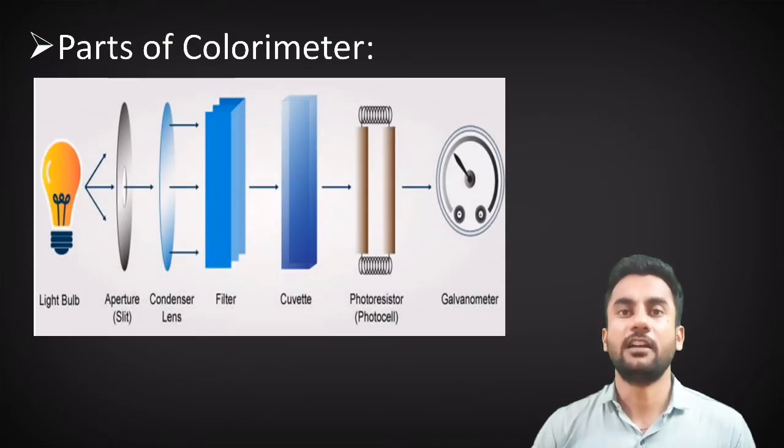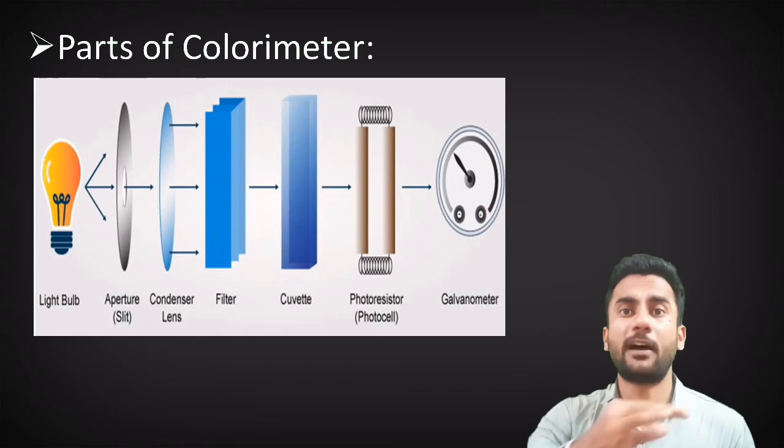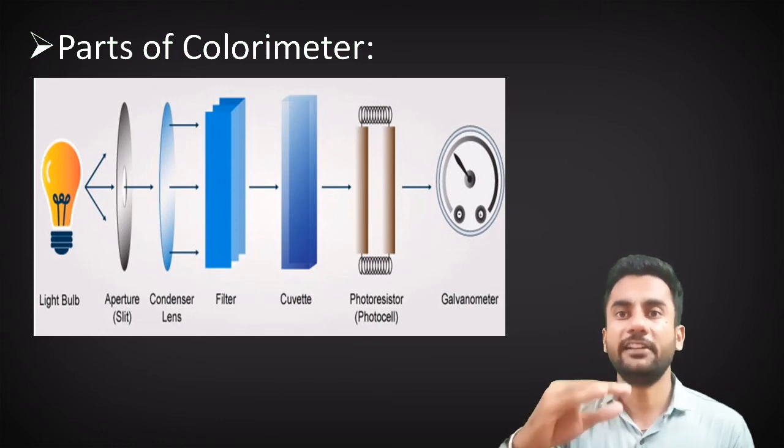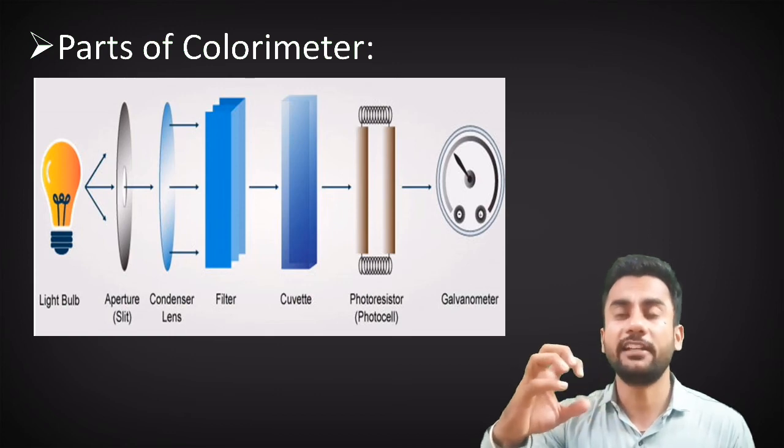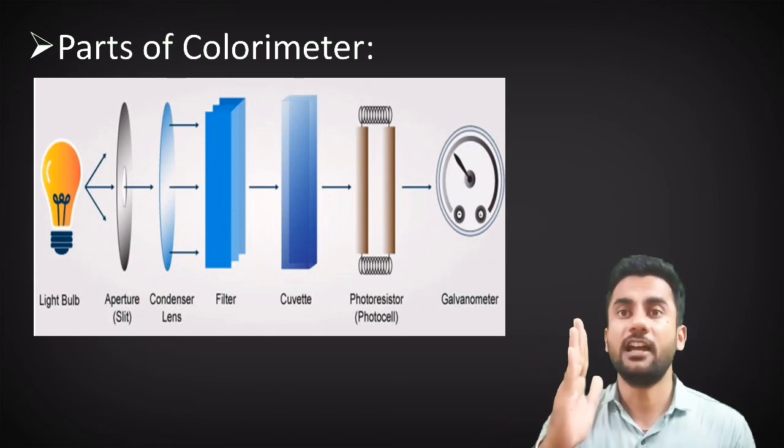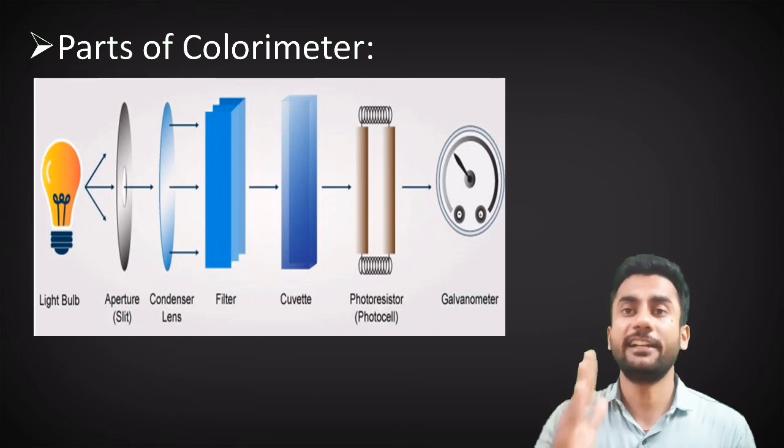Now let us see the parts of the colorimeter. The light from the bulb is allowed to pass through the slit, condenser, filter, and the cuvette containing the sample. The radiation coming out from the cuvette is allowed to incident on the photocell. This photocell converts the optical signal into electrical signal which can be noted on the galvanometer.